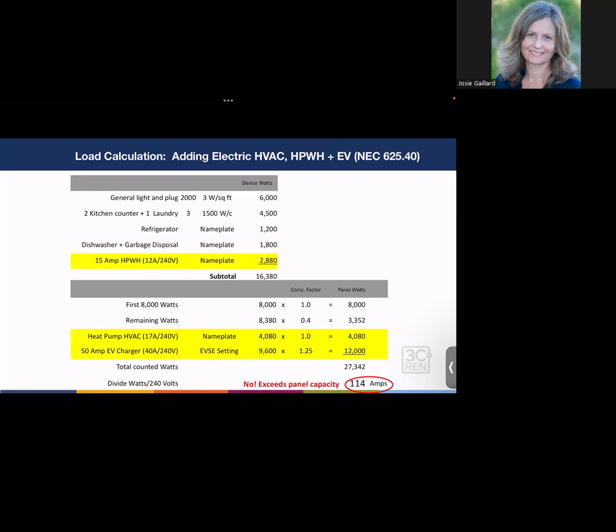And for that, we get total panel watts of 12,000. So total counted watts is 27,342 divided by 240 volts for whole home voltage, and you get 114 amps, which exceeds our panel capacity of 100 amps. So it doesn't work. Back to the drawing board for this house.